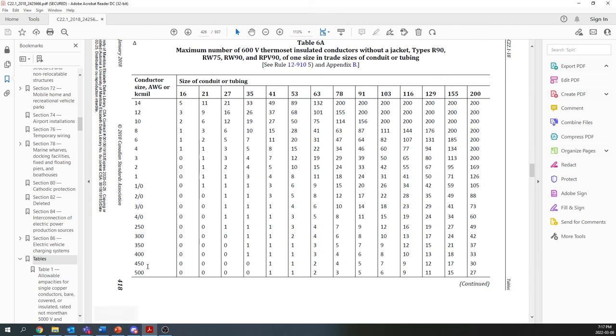If you had, for some reason, 400 kcmil and number eights in the same conduit, you're not going to want to approximate your number eights as 400s. But for this case, number two, number four, it's pretty close. And in this sense already, there's no three conductors here, right? So we have to go up to another one. Now, mind you, we actually have to account for six number twos. So we would actually have to go up to this 53 or 2-inch trade size conduit.